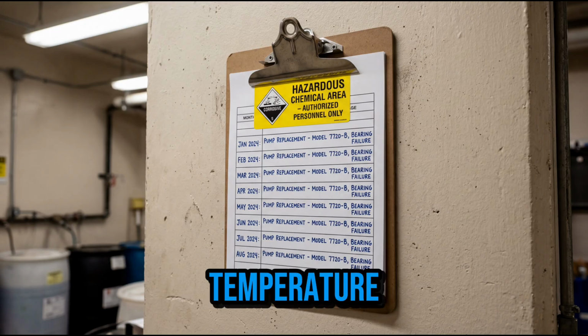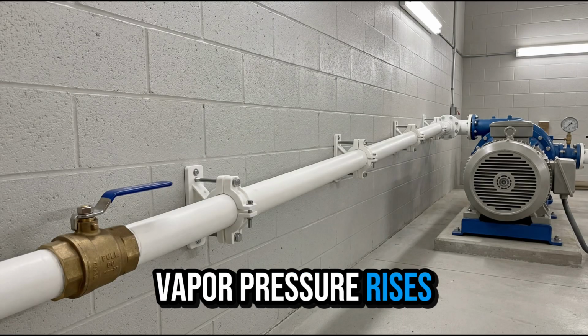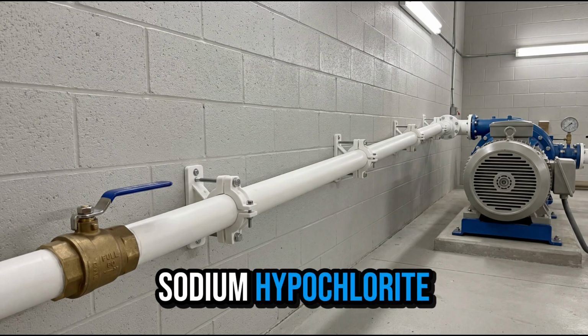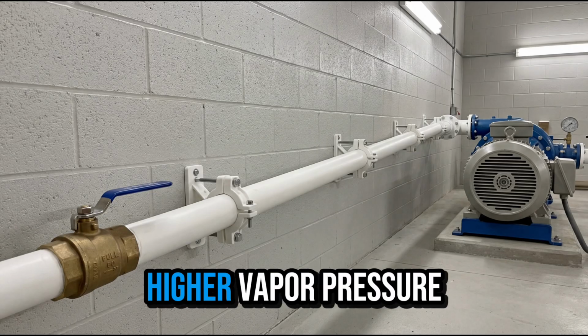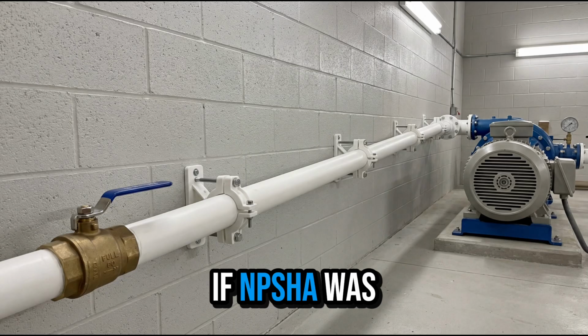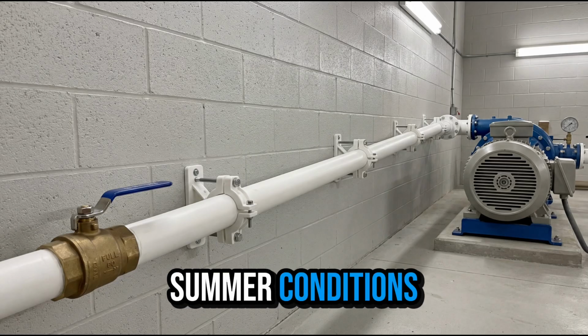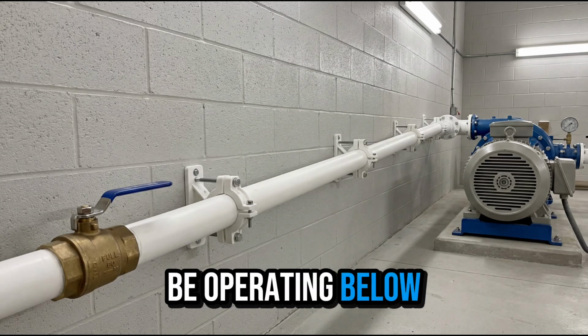Fifth is fluid temperature. Vapor pressure rises with temperature. Sodium hypochlorite in a hot environment has much higher vapor pressure. If NPSHa was not recalculated for summer conditions, the system may be operating below NPSHr.